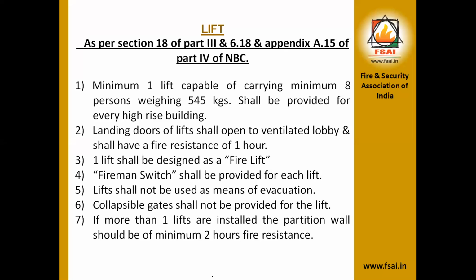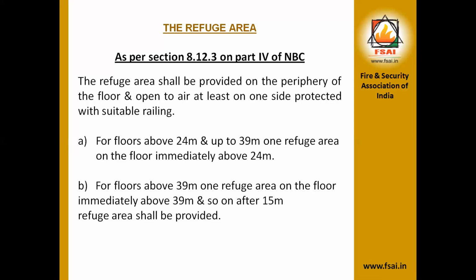Fireman switch shall be provided for each lift. Lift shall not be used as a means of evacuation. So at the time of evacuation, you should not use the lifts. You should use the staircases. Collapsible gates shall not be provided for the lift. If more than one lift is installed, the partition wall should have minimum 2 hours fire resistance. Next is the refuge area. There are some norms for the refuge area. As we have seen in the last slide, the refuge area. Now we can understand the technical specification. For floors above 24 meter and up to 39 meter, one refuge area on the floor immediately above 24 meter.